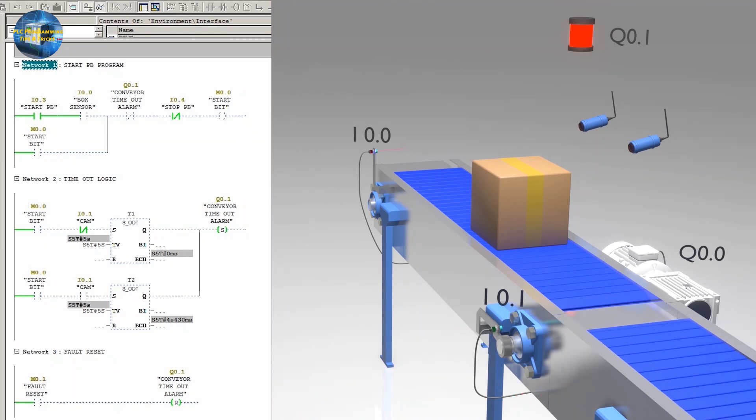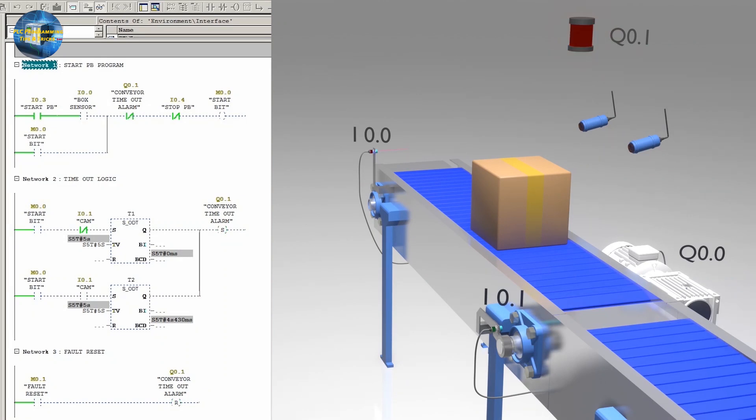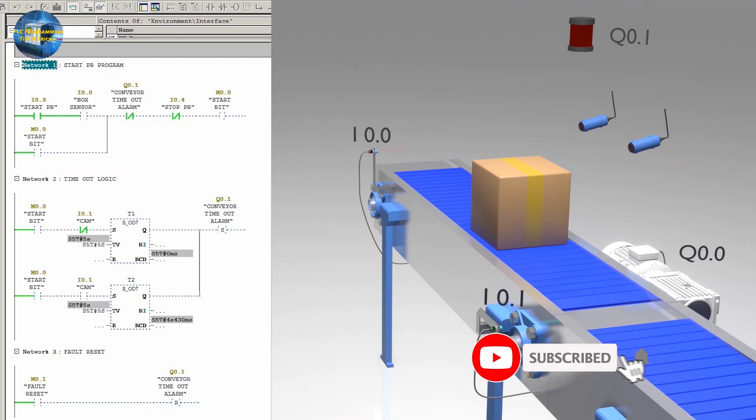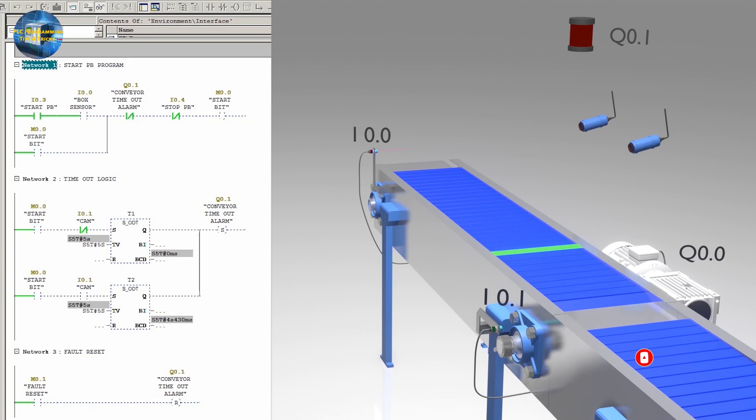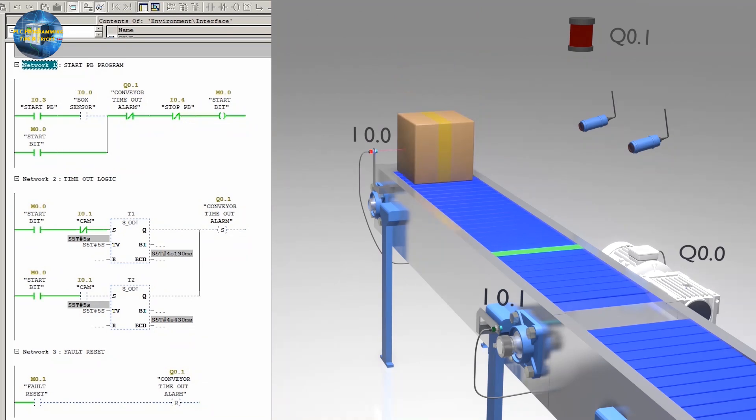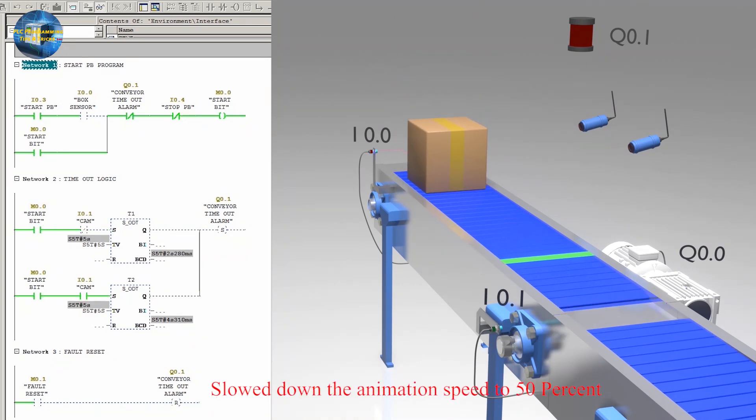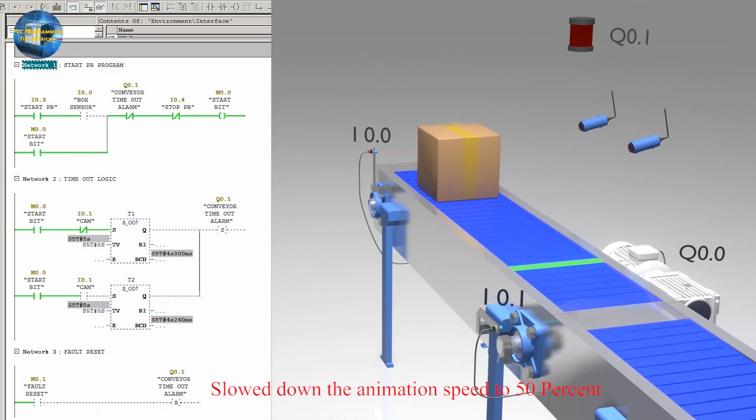Now we will reset the alarm bit by activating the reset bit M0.1. Now let's test the second condition. We will start the process by pressing the push button I0.3. As soon as the box comes in front of the sensor I0.0, the conveyor belt motor starts.